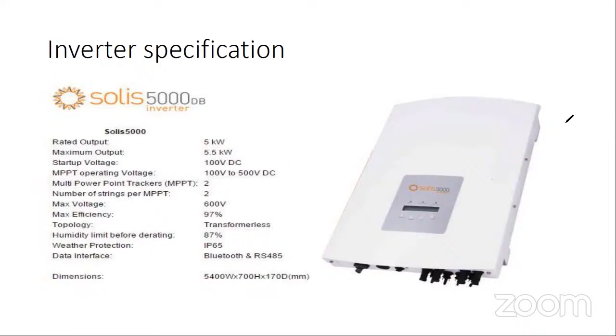Technically speaking, there are two main MPPTs. Under that, string 1 and string 2 are there, and again string 1 and string 2. So even if you connect in string 1 or string 2, they both get paralleled inside MPPT 1. Similarly, wherever you connect, it gets paralleled inside that MPPT. So this is the understanding. So now we know that 2 strings can be given. In one string, we can give a maximum of 12 panels.